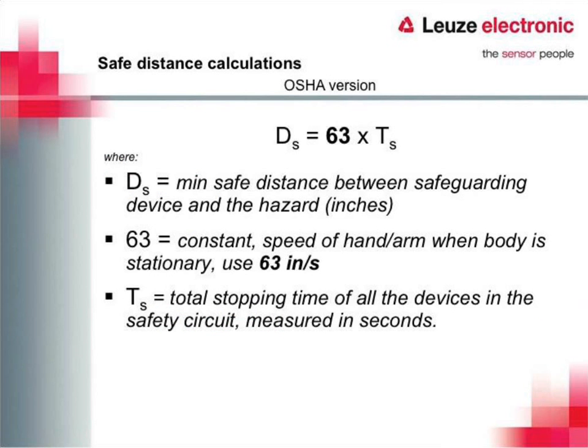The OSHA calculation is: Ds (minimum safe distance) equals 63 times Ts, where Ts is the stopping time of the machine. You can take the stopping time of the machine and add the response time of the light curtain and the response time of the relay, or you can do a safe distance stopping measurement, which gives you all of this in one number — a service Leuze can perform for you. OSHA specifies 63 inches per second as the speed of a hand. To simplify: if your machine takes one second to stop, then the light curtain needs to be mounted 63 inches away. It's very important to know the stopping time of the machine because it dictates how close or far we have to be.